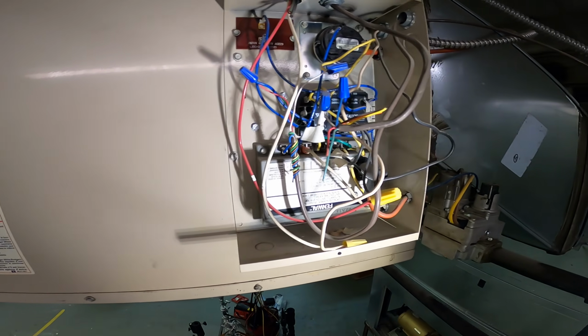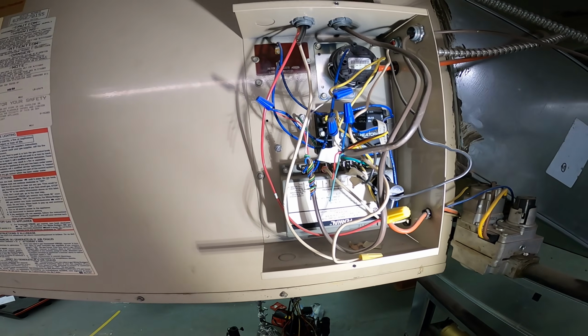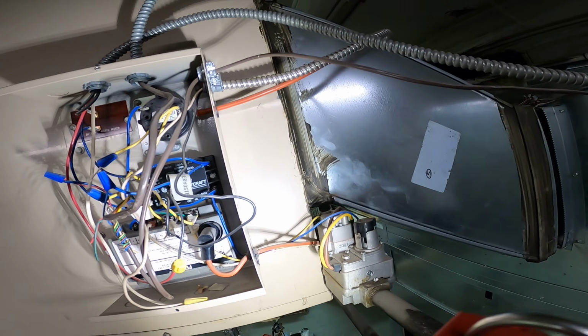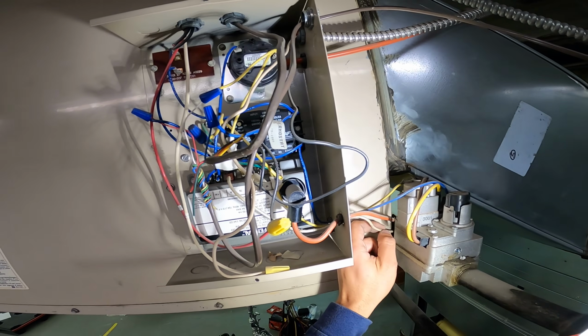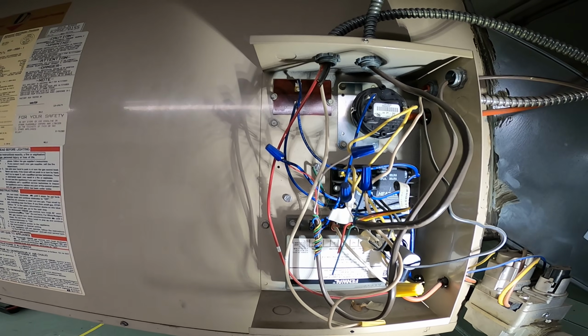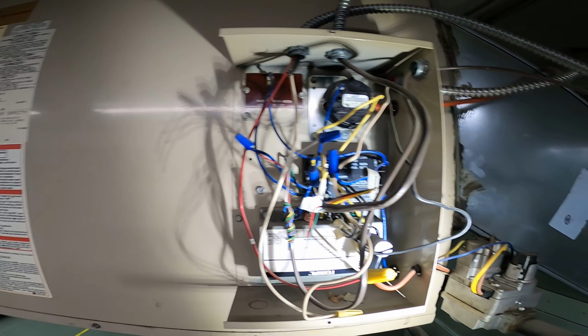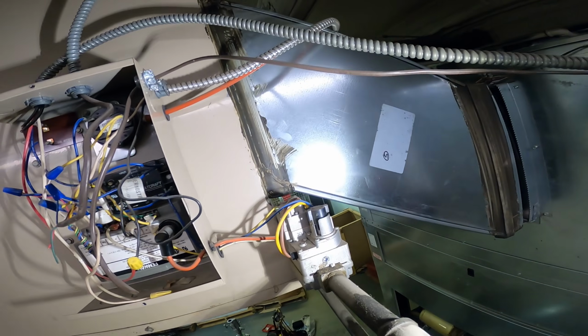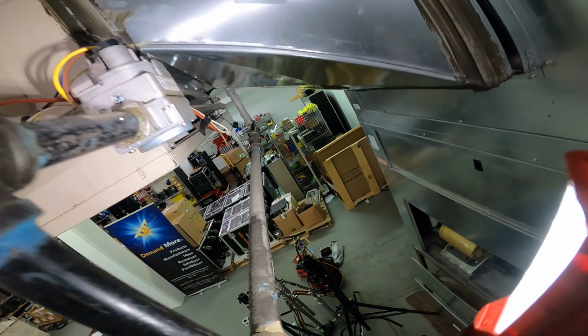Coming out the ignition control is this thick orange wire. All right, that's going to be your spark. Then you have another one, which is like a braided wire. And what's that right there? S1, that's going to be your flame sensor. And that sits inside of the burner section.